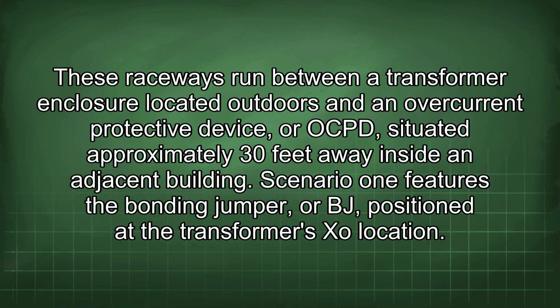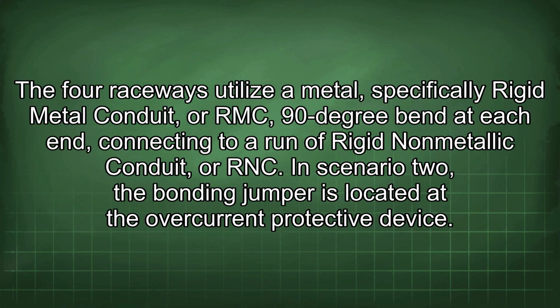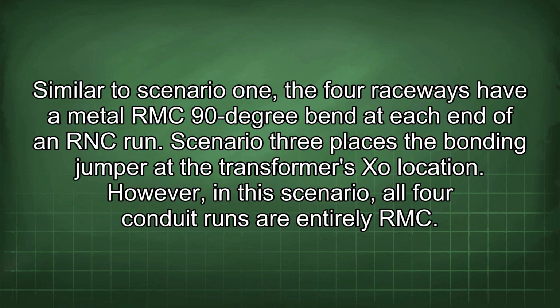Scenario 1 features the bonding jumper, or BJ, positioned at the transformer's XO location. The 4 raceways utilize a metal, specifically rigid metal conduit, or RMC, 90-degree bend at each end, connecting to a run of rigid non-metallic conduit, or RNC. In Scenario 2, the bonding jumper is located at the overcurrent protective device. Similar to Scenario 1, the 4 raceways have a metal RMC 90-degree bend at each end of an RNC run.